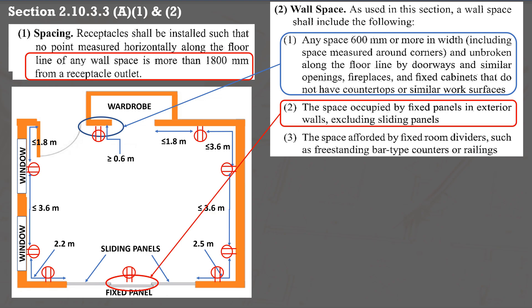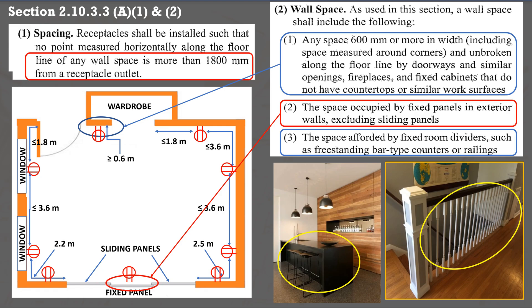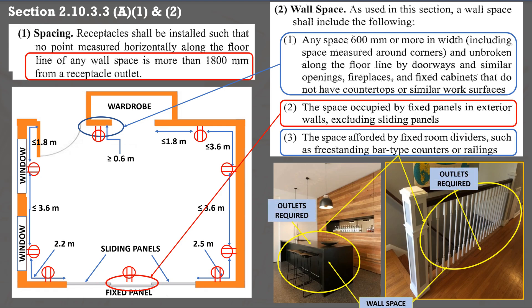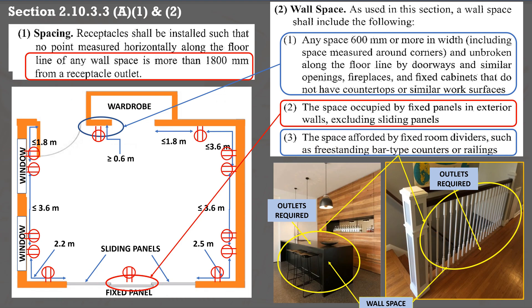Hence, an outlet is required for the space afforded by fixed room dividers, such as freestanding bar-type counters or railings. This divider and railing are considered wall space, so outlets are required. This layout complies with the minimum requirements of section 2.10.3.3 A1 and A2 of the PEC. You can have more outlets as needed, just ensure that no point on the wall is more than 1,800 mm from a receptacle outlet, and the maximum spacing between two outlets is not more than 3,600 mm.